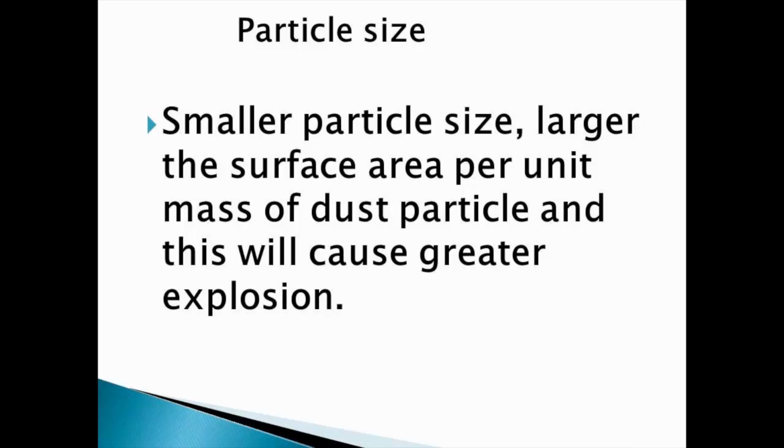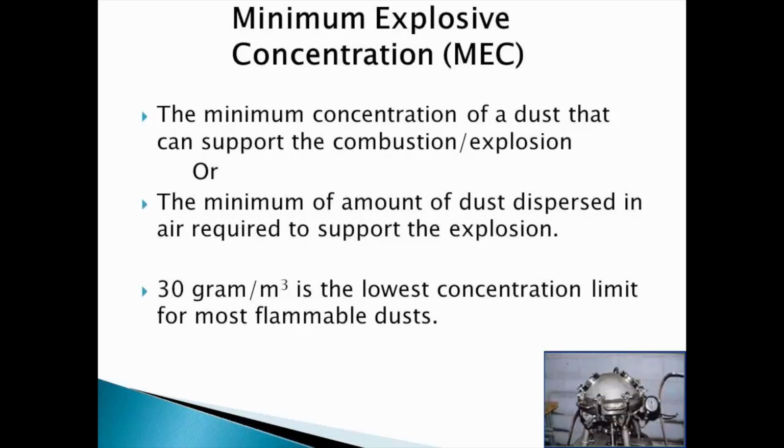In general, a decrease in particle size increases the likelihood of occurrence of a dust explosion, as well as its consequence severity. The MEC, MIE and MIT all decrease with decreasing particle size. This is due to the surface area effects, where a smaller particle has a larger surface area and therefore enhanced reactivity.